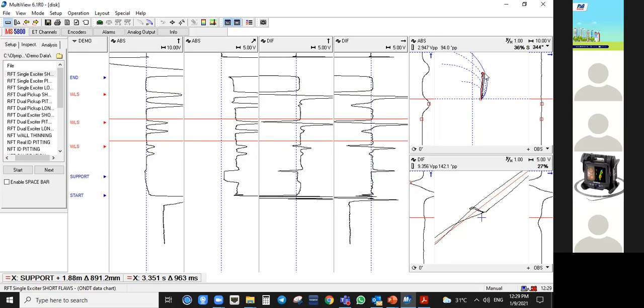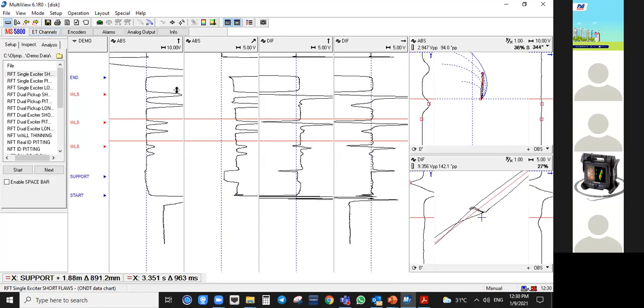Sorry, 15 to 20 degrees difference. Okay, so if you want to change that, you go to your MS5800 here. Oh, sorry, you go to ET channels here, and then you change your frequency here. If the angle is too wide, you lower your frequency, maybe make it 0.18. If the angle between two defects is too shallow or too narrow, maybe less than 15 degrees, then you increase the frequency. Then you run it again.